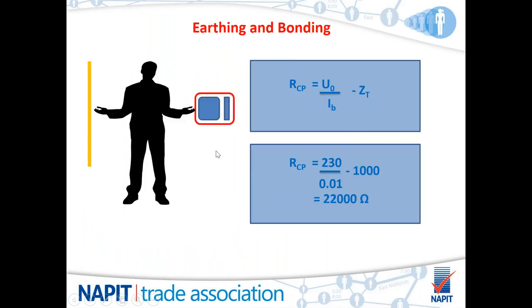And as you can see from our diagram, we have a gentleman being able to touch an exposed conductive part and a piece of metalware that we're trying to assess. If we do the equation and we take 230 volts as the nominal voltage, then we say we don't want more than 10 milliamps to go through our person and give us a rough ohmic reading of 1,000 ohms for the resistance of the body. You can see if you do that sum, we get 22,000 ohms. And Guidance Note 8 gives reference to this, in the fact that if the resistance between the exposed conductive part and the metalwork under consideration is over 22,000 ohms, then the current flowing through a body would be so imperceptible that there is no requirement to bond it.